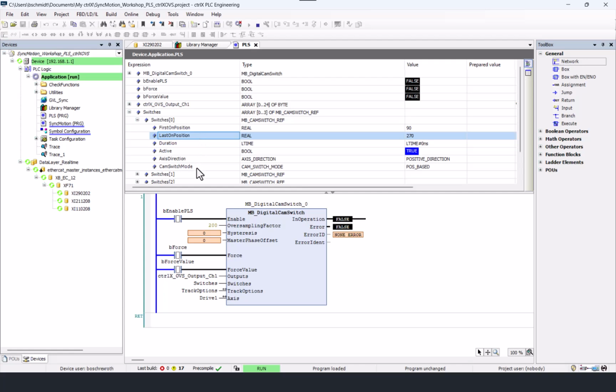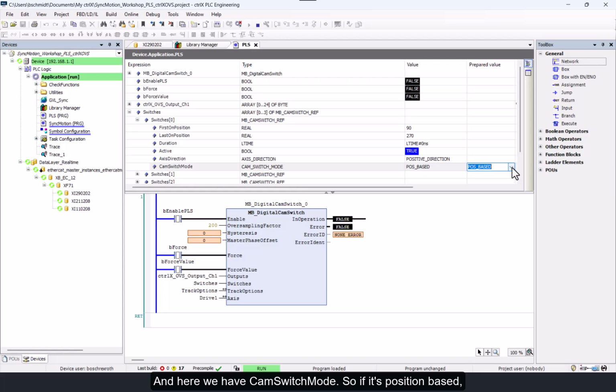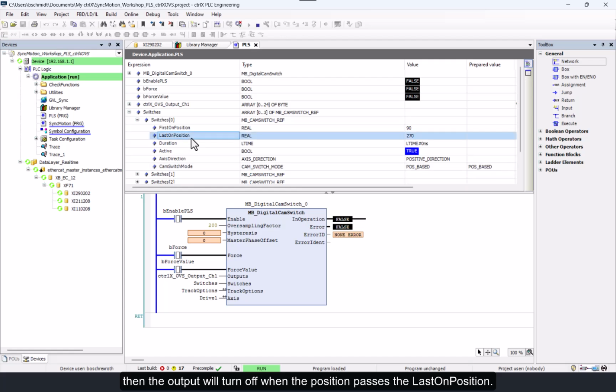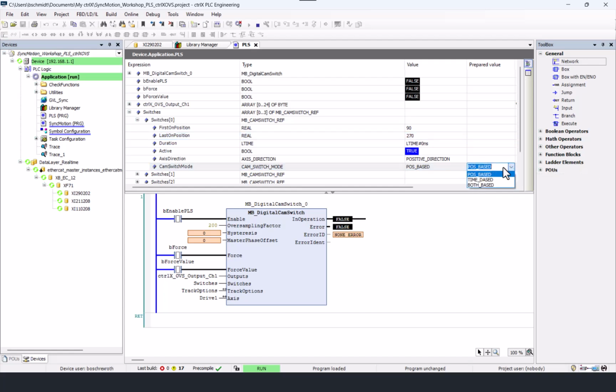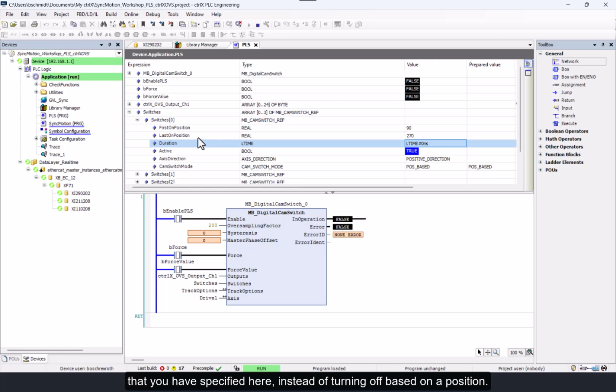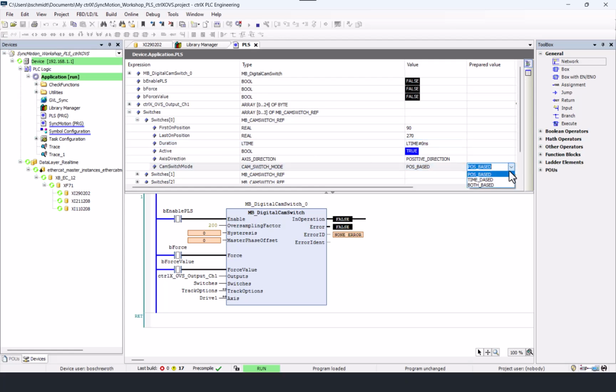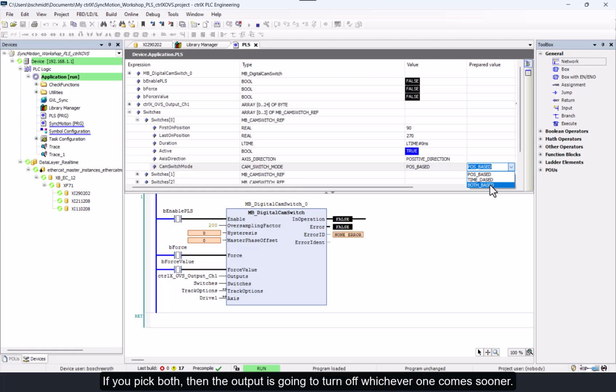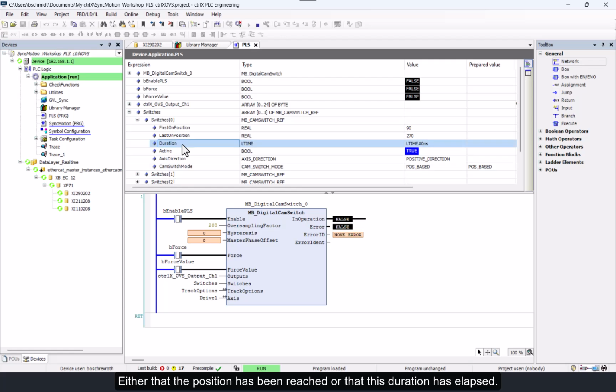Down here we have cam switch mode. So if it's position based, then the output will turn off when the position passes the last on position. If it's time based, then it's going to stay on for the duration that you have specified here instead of turning off based on a position. If you pick both, then the output is going to turn off whichever one comes sooner, either that the position has been reached or that this duration has been elapsed.